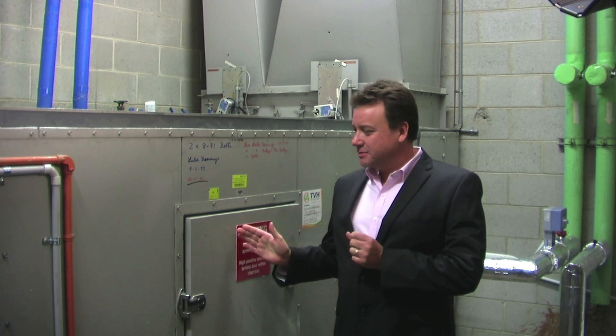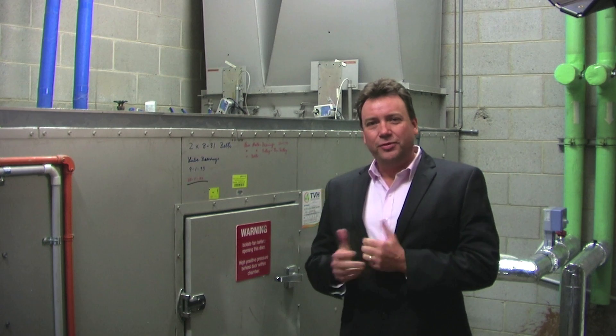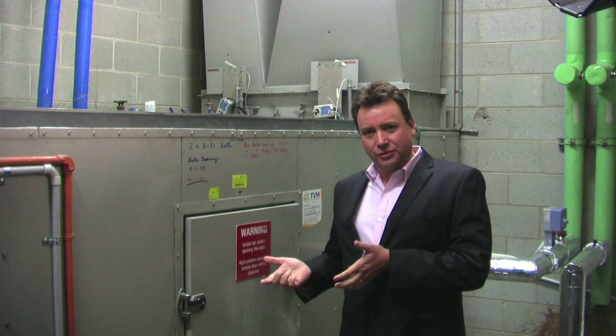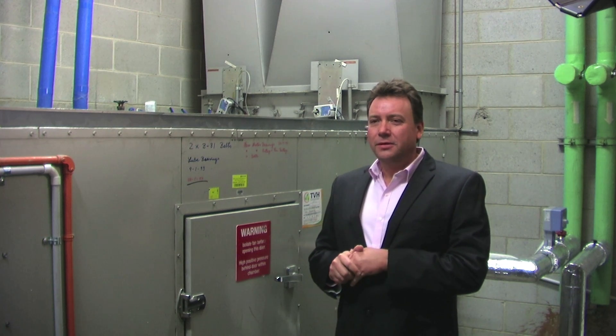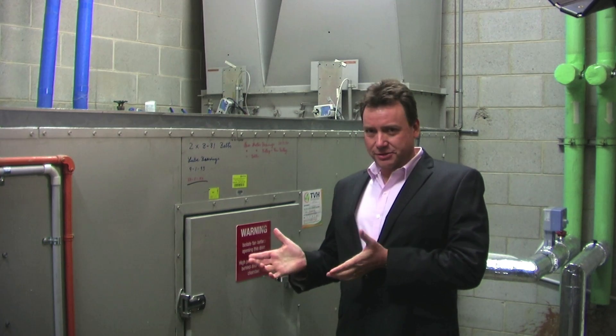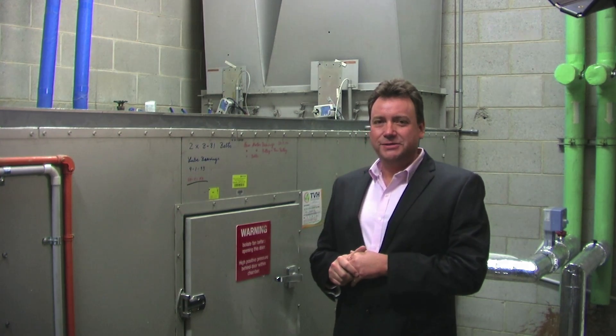We're looking at one of the typical air handling units that are installed at Wakefield House. Systems Solutions Engineering were brought in by the client because the air handling units were struggling to deliver the cooling capacity to the floor plate. So we teamed up with ebm-papst to address the fan situation as we thought we were able to improve the ventilation on the floor.